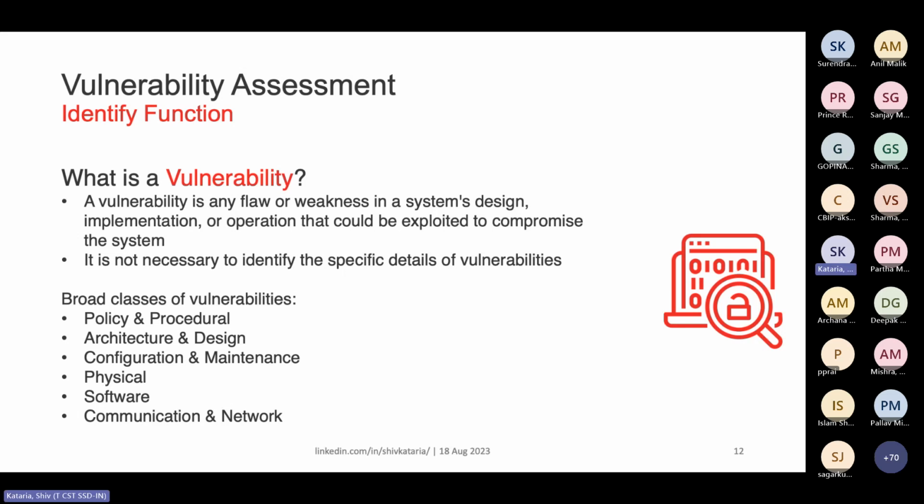And typically in industrial control systems, we see lots of network level vulnerabilities because we leave the configuration to the OEMs. We don't give them the requirement for a network configuration. We don't provide the network ranges. We don't give the hardening requirements. And the OEMs or system integrators take it in their hand and their focus is to finish the project and configure it the way they have been doing it so far.